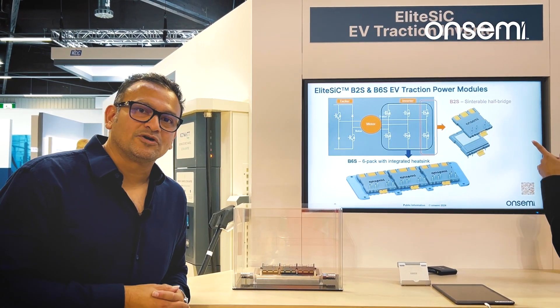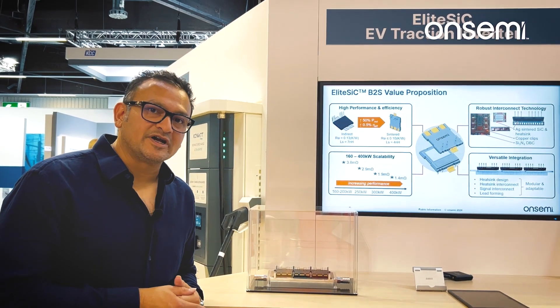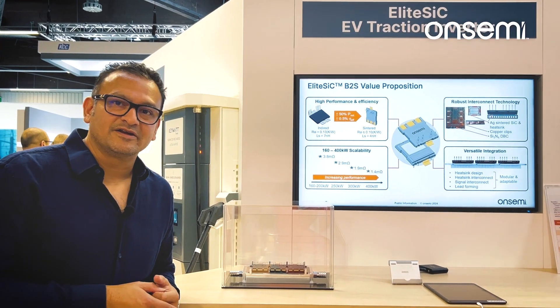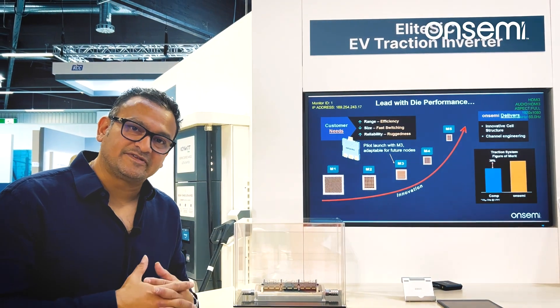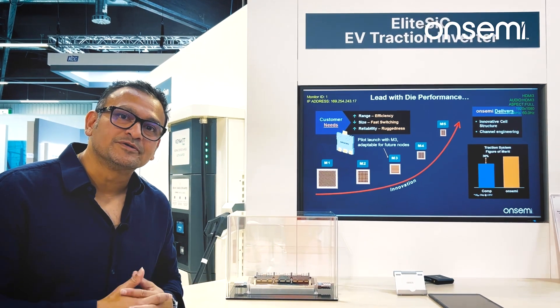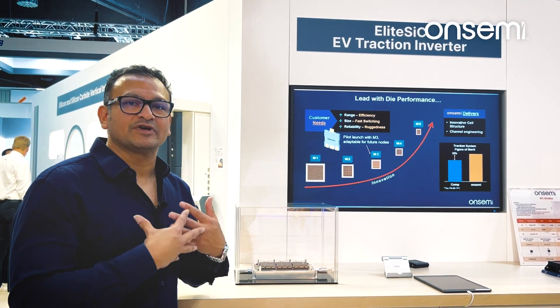For efficiency, we have our latest M3E silicon carbide technology, 1200 volt rated. The power modules are very low in stray inductance, under 4 nanohenry. Thermal resistance is under 0.1 Kelvin per watt. This keeps the silicon carbide chips cool and lowers losses and improves efficiency.